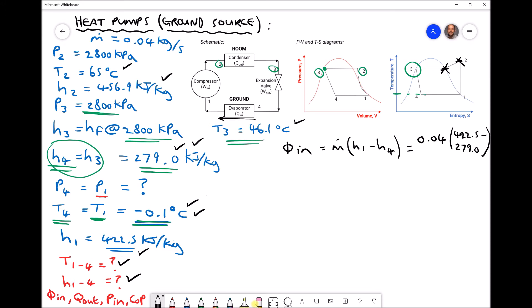Giving us a rate of heat transfer into the process in the evaporator equal to 5.74 kilowatts. The reason it's kilowatts is because our enthalpy values are already expressed in kilojoules per kilogram. So the two values in the brackets are actually times 10 to the 3. But as we're working in kilojoules on the table and we want an answer in kilowatts, we can work with the raw values, providing we remember that our units are in kilowatts.